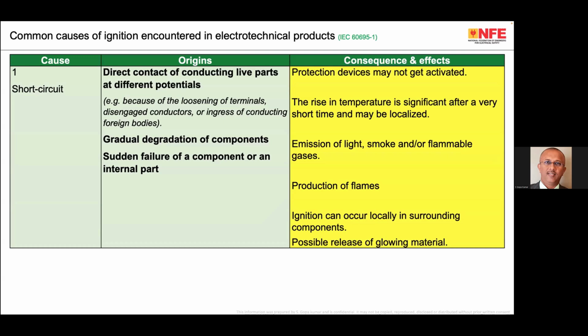Short circuit is a direct contact of live parts at different potentials. Please note that a contact between a live conductor and earth is not called a short circuit. It is called an earth fault. So here, short circuit means there is a contact between live conductors, phase to phase or phase to neutral.